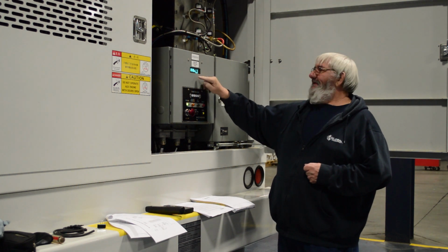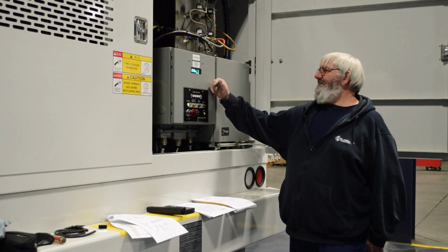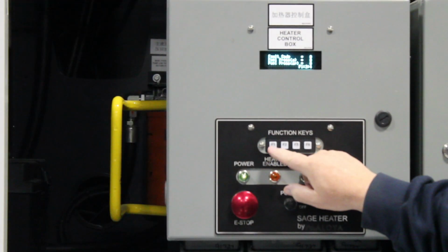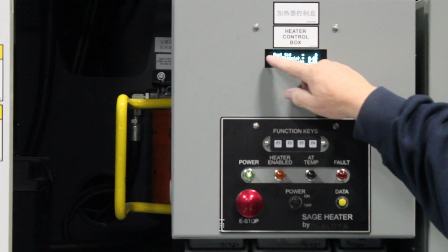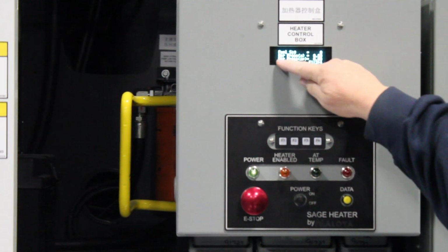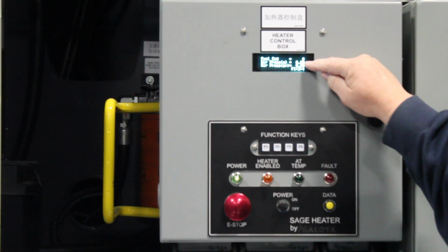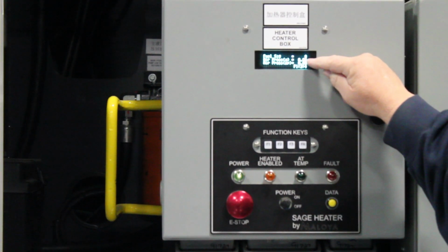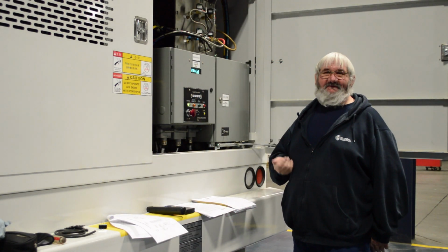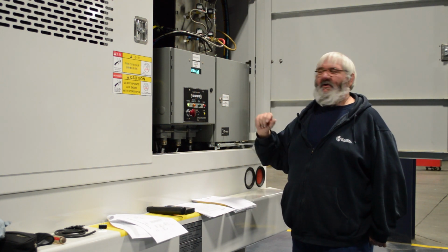Now let's take, for example, if these two numbers were the same. If your fuel pressure actual and your fuel pressure set point are the same, then you can scroll down, look at your fuel signal, air pressure actual, air pressure set point. Now remember, your fuel signal will vary between 0 to 2650. So if your signal is over 2650, then this is another indication that you have a fuel problem. But let's say that it is in the correct parameters.